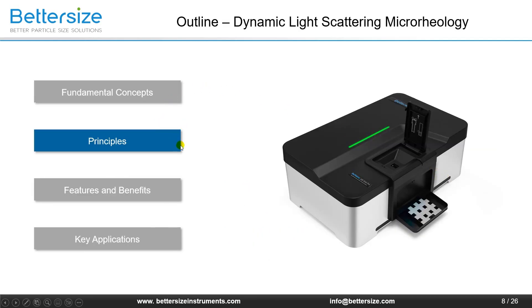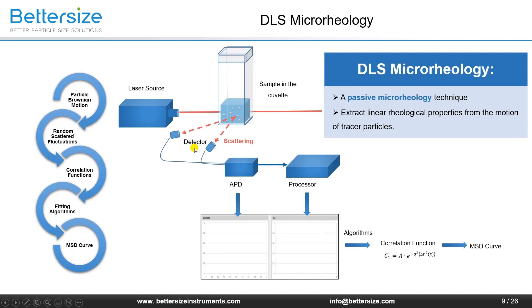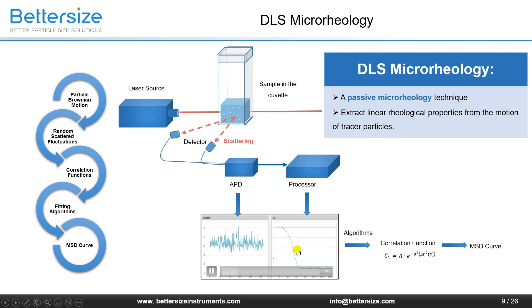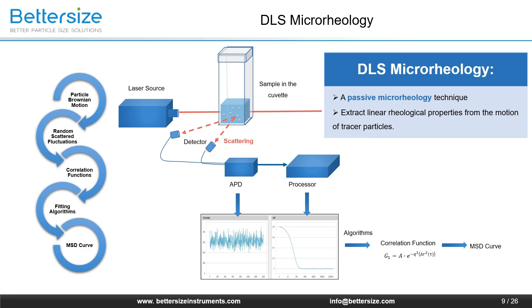Let's move on to the principles of DLS microrheology. DLS microrheology is a passive microrheology that applies no external forces to the tracer particles, and it can extract linear rheological properties from the motion of tracer particles undergoing thermal fluctuations in a system. In a DLS microrheology experiment, tracer particles undergo Brownian motion at thermodynamic equilibrium. The motion of the tracers causes random scattering fluctuations, and DLS microrheology measures the autocorrelation function of the light scattered by the particles. The relation between the MSD of the tracer particles and the autocorrelation function is then obtained from the correlation function.